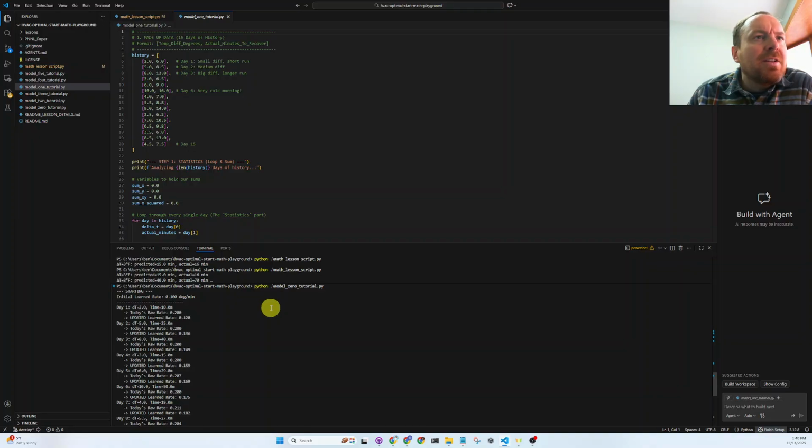Alright, we can walk through this script here, but it's actually printing delta temperatures. Remember, this is the zone temperature before the building starts, and then the delta of the occupied zone set point. So in this first day we're either 2 degrees above or below the occupied zone set point, and recorded time of 10 minutes.